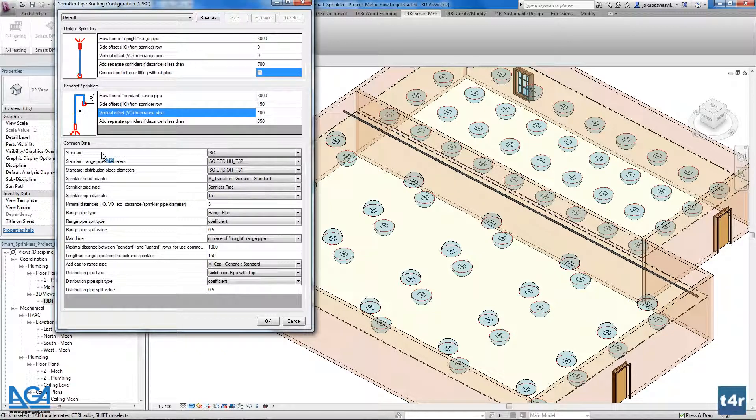Going further, we have the standard range pipe diameter and the standard distribution pipe diameter. These functionalities allow you to choose from predefined overall system range pipe diameter and distribution pipe diameter standards. These standards define rules for system calculation — for example, the maximum number of sprinklers per range pipe with one diameter. You can also define your own standards by creating a folder with a standard name and modifying text files inside these folders.